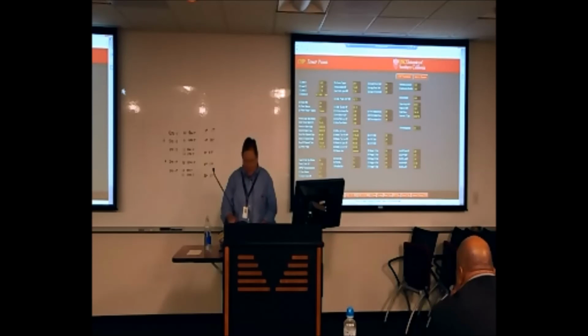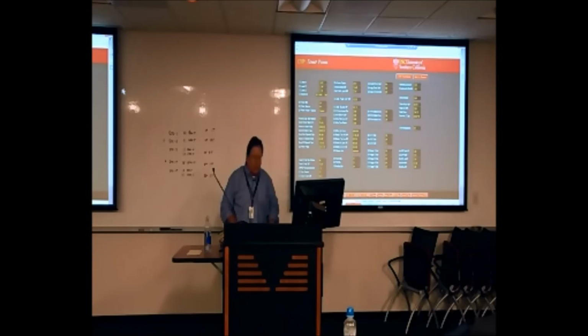And then Craig, you and I can get together anytime. We can look at this and kick things around. We've got to put these in the auto mode and watch each one run for a while. We have that alarm problem we have to diagnose yet. So you and I will still be interacting on this. I haven't seen it in alarm. Yeah, I've checked it a couple times myself and I haven't seen it either. Though one thought I had is we could just lengthen that alarm delay. Right now I think it's 30 seconds. Maybe I could grow that a little bit. If it's just going in and out, I could mask it by doing that. But of course that might be masking a problem that just shows up later on anyway. But we can brainstorm a way to see if it's at the drive or at the Honeywell end.